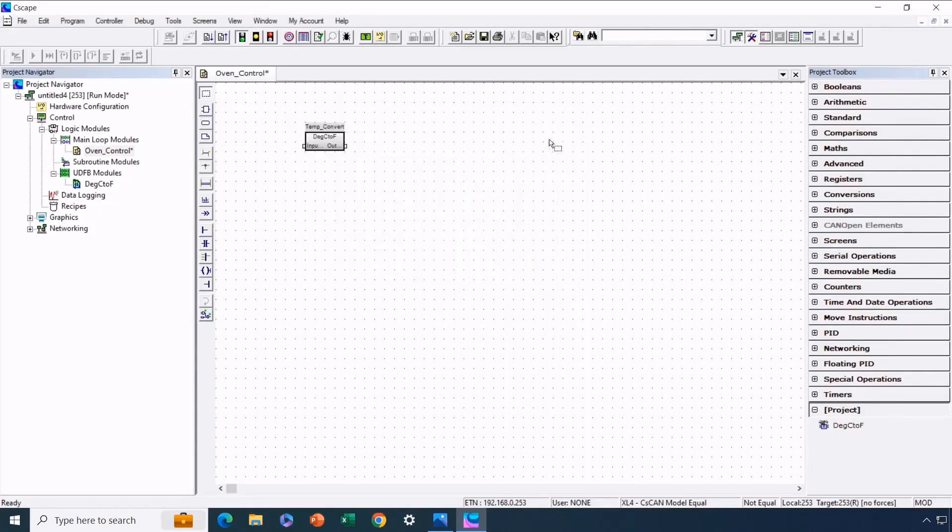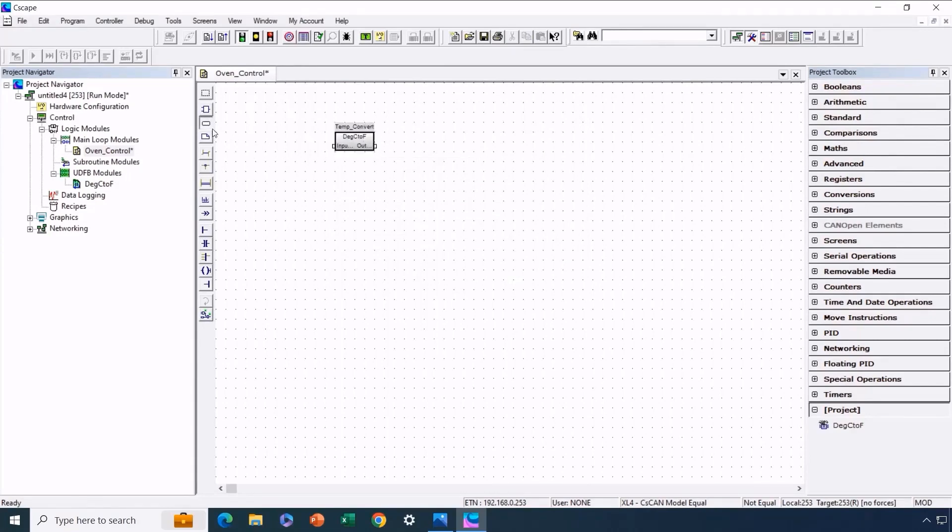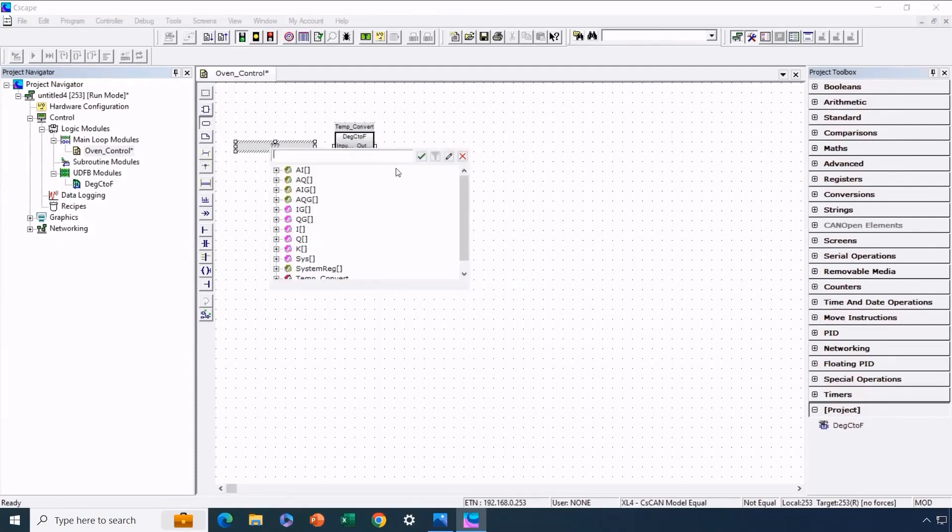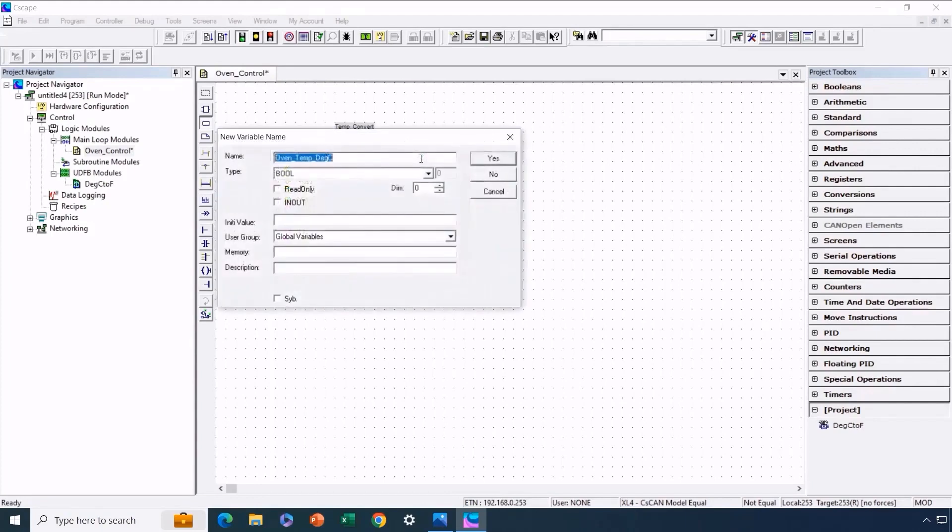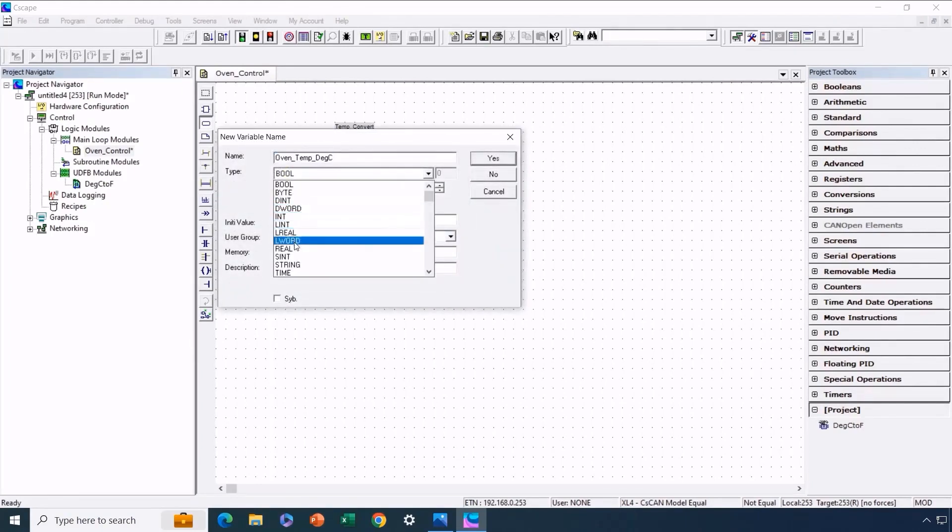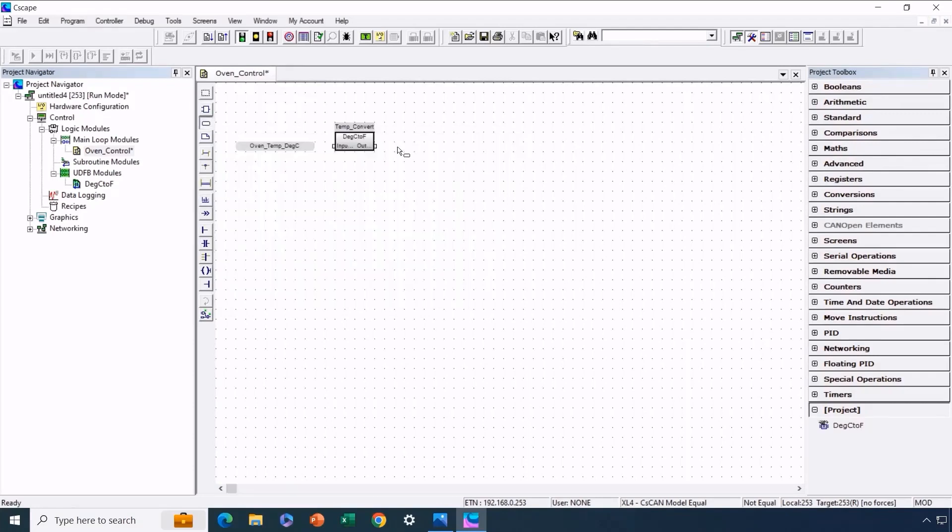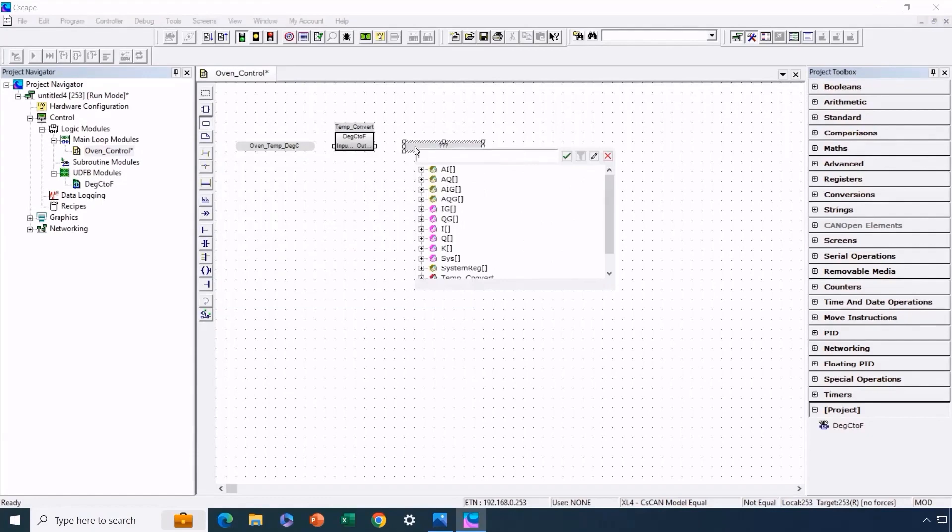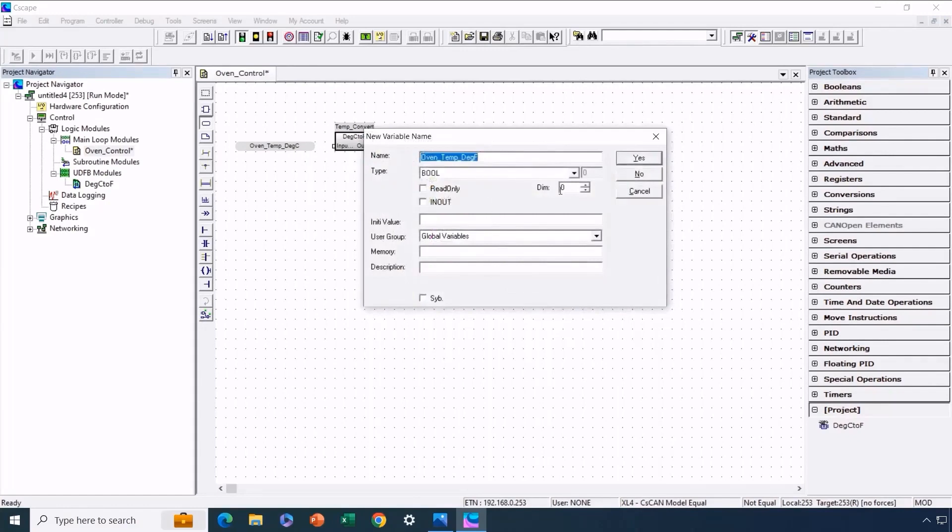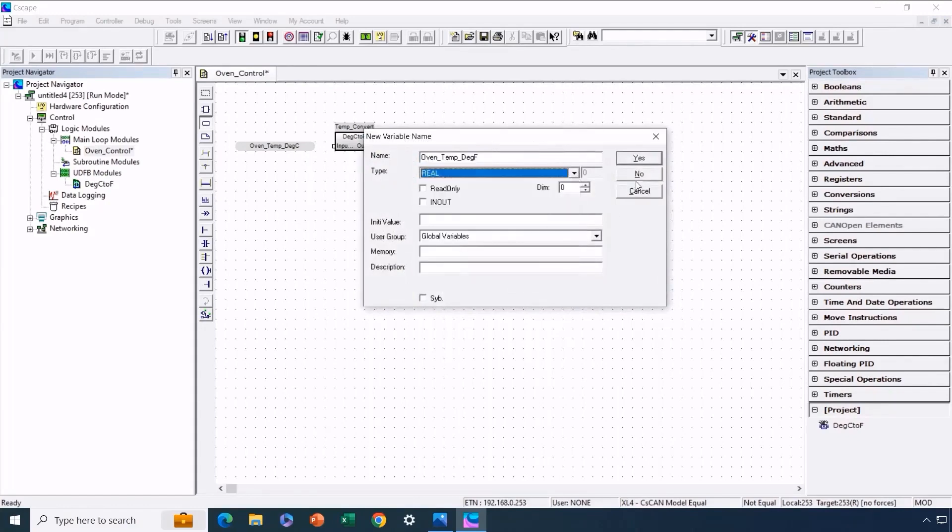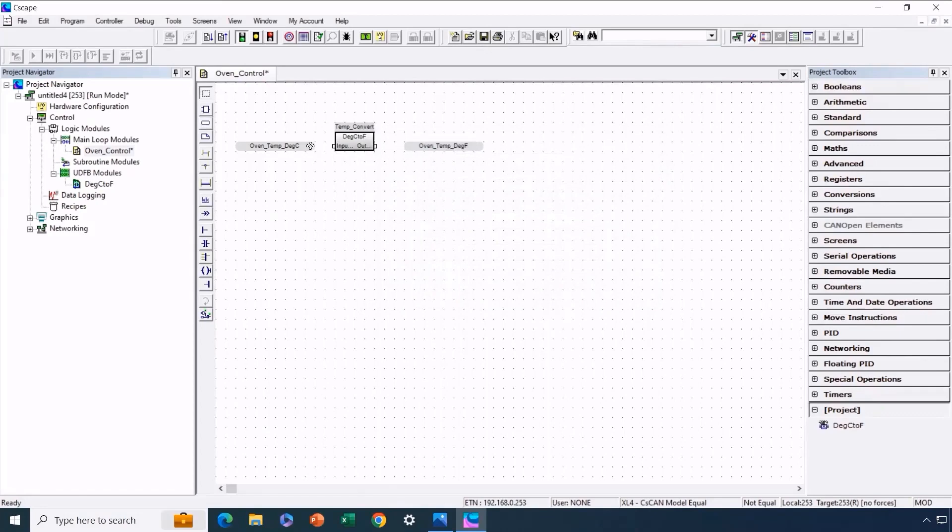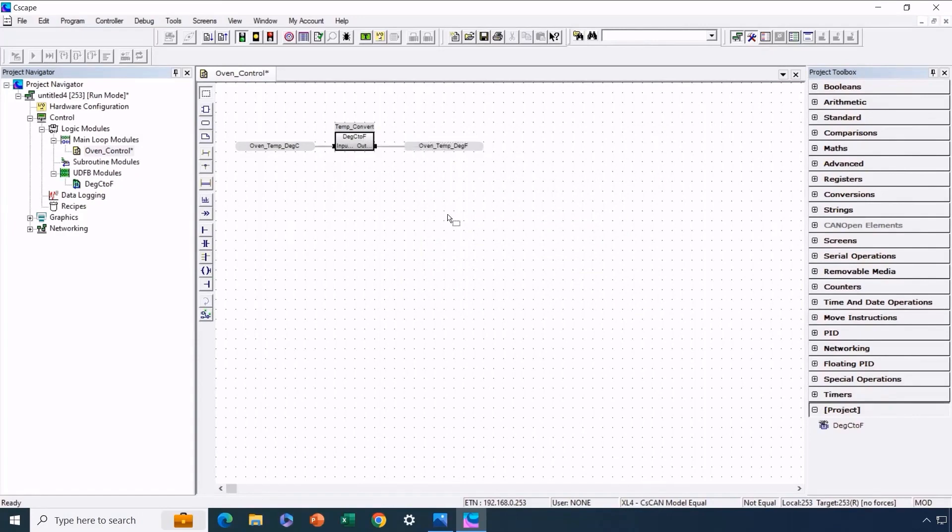We'll specify the type as the user-defined function block. Everything seems correct. Now the next step is to place values on the screen. We'll position this here. Upon double-clicking, it becomes the input variable for the project. For instance, let's say TempDegreeC. This is created on the fly. It is essential to ensure that we select the correct variable type, a floating point value, not a boolean. Here's the other side of the function block, where we need to place this OvenTempDegreesF. We'll choose the appropriate variable type again. Now it's a simple matter of connecting these to the input and output, ensuring proper connections are made. There we have it, our function block diagram logic, utilizing a UDFB that we originally created in ladder logic.